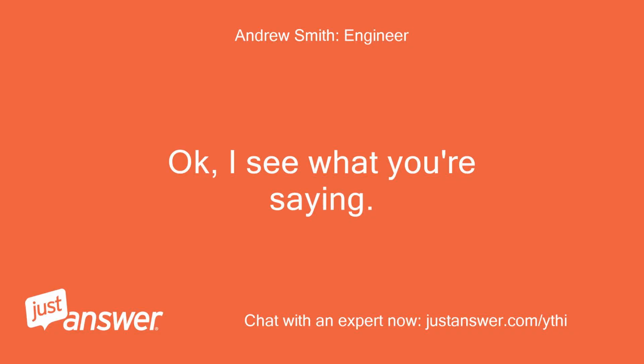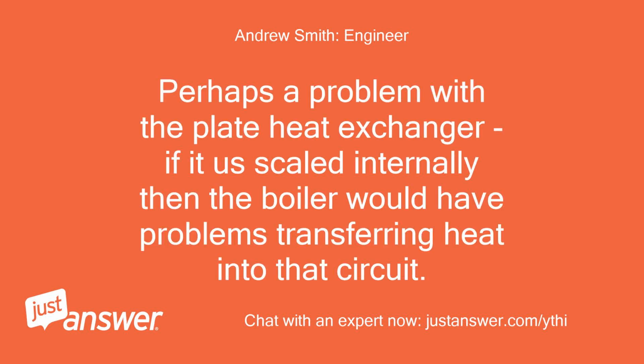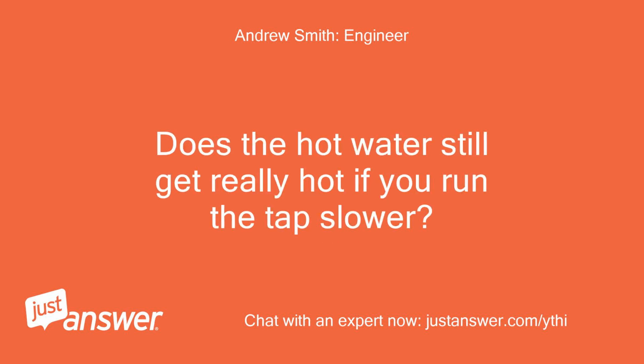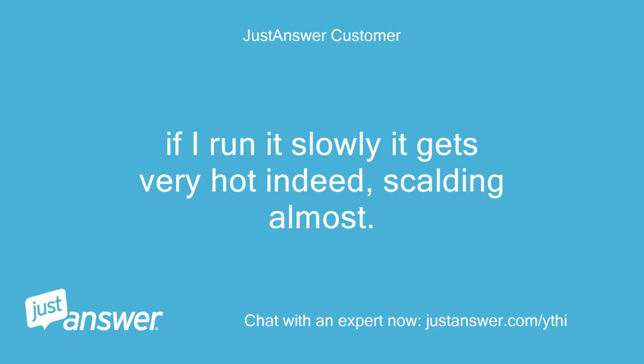Okay, I see what you're saying. Perhaps a problem with the plate heat exchanger. If it is scaled internally, then the boiler would have problems transferring heat into that circuit. Does the hot water still get really hot if you run the tap slower? If I run it slowly it gets very hot indeed, scalding almost.